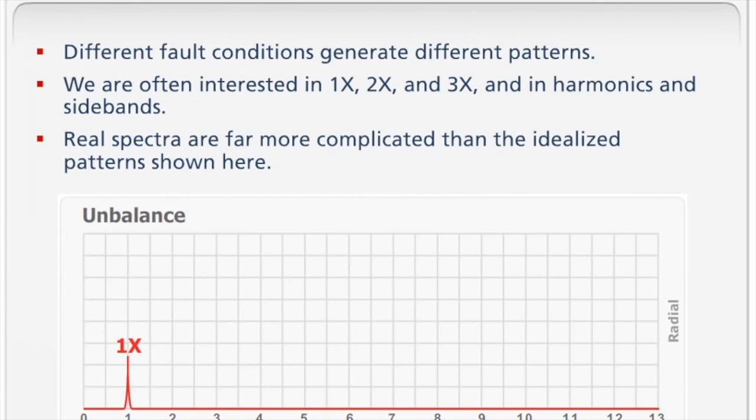But if I do have unbalance, the 1x peak goes up. If there's resonance, it amplifies the vibration, and we tend to see the base of the peak sort of broaden out.